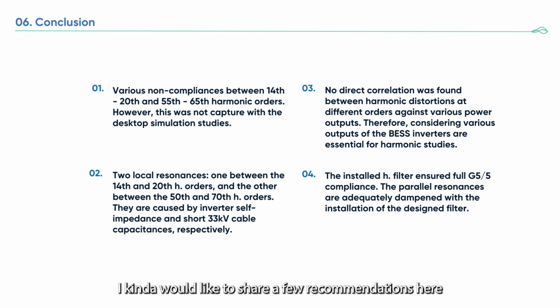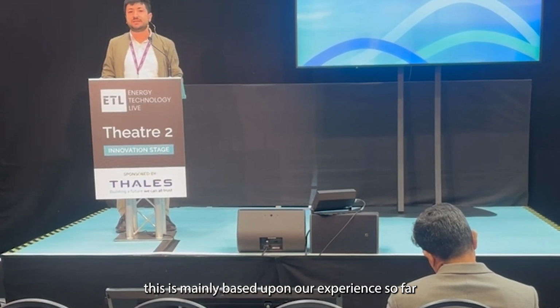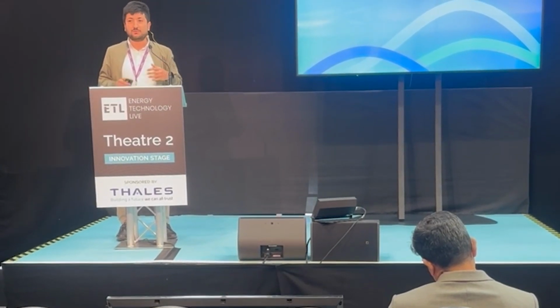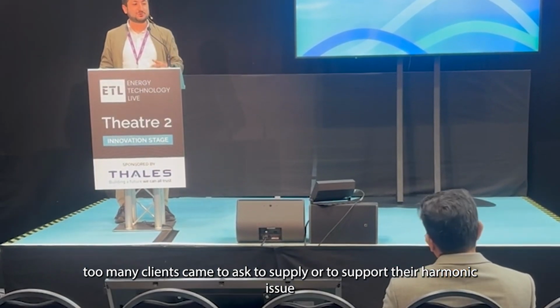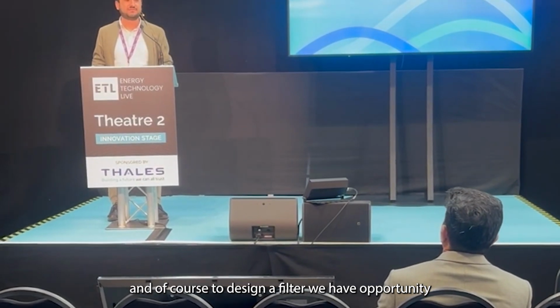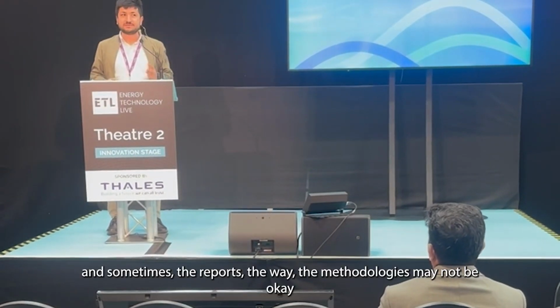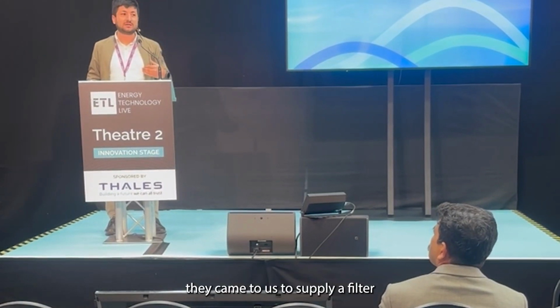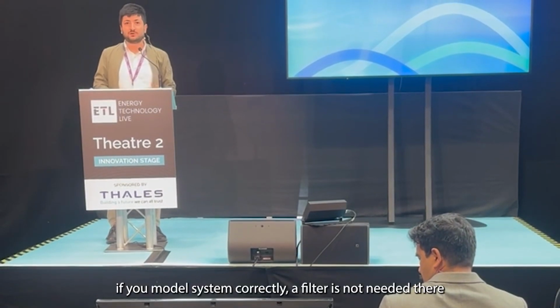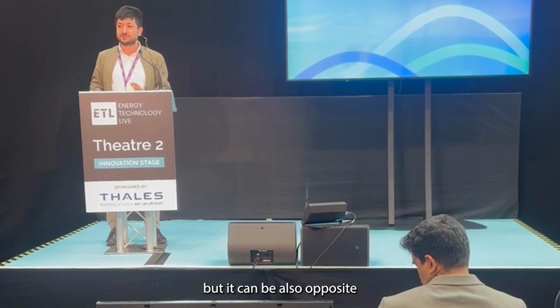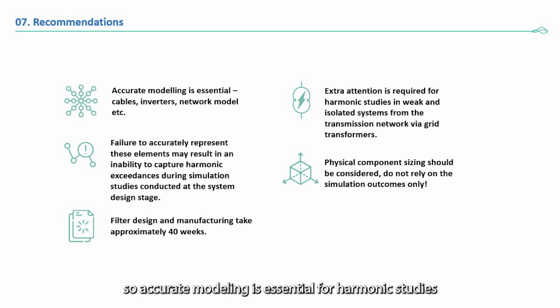And I kindly would like to share a few recommendations here. This is mainly based upon our experience so far. Considering we are a consultancy company and manufacturing company, too, many clients came to us to supply or to solve their harmonic issue. And of course, to design a filter, we had opportunity to review their G5/5 reports. And sometimes the reports, the methodologies may not be okay. They came to us to supply a filter, but when we look at the model, if we model system correctly, filter is not needed there. So it can be also opposite. So accurate modeling is essential for harmonic studies, especially network model, inverter self-impedance, and cables. They are three key parameters for harmonic studies.